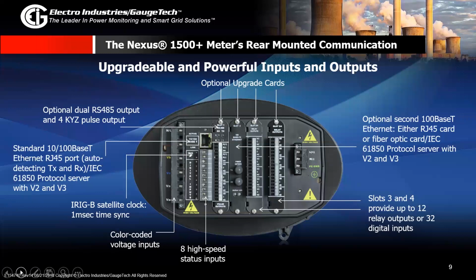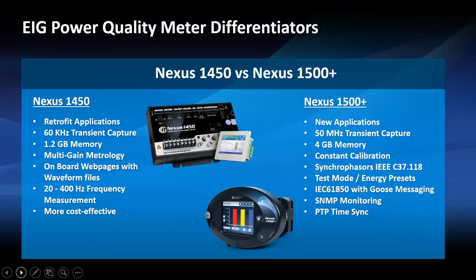So we talked about the 2 meters separately. They're both high quality power quality meters, but what are some of the differences between them? How do you know when it's more appropriate for a 1450 or when a 1500 Plus may be more appropriate for you? So the 1450 is good for retrofit applications, whereas the 1500 Plus is good for new applications. The 1500 Plus also does higher transient captures up to 50 megahertz and has 4 gigabyte of memory, whereas the Nexus 1450 can do transient captures of up to 60 kilohertz.